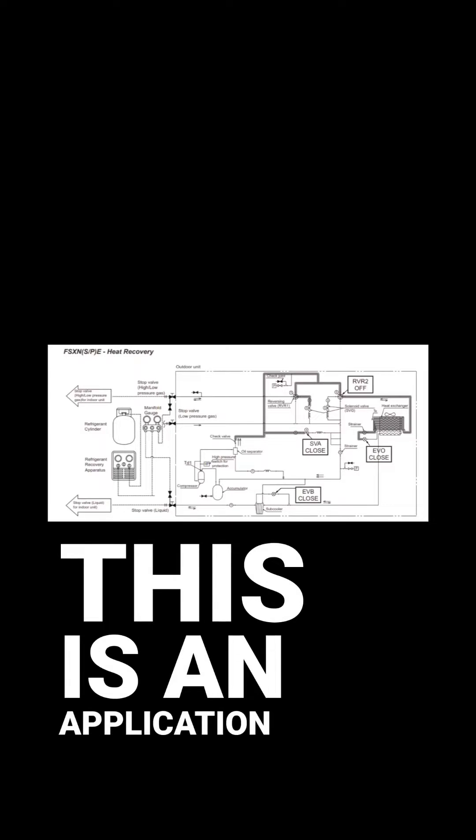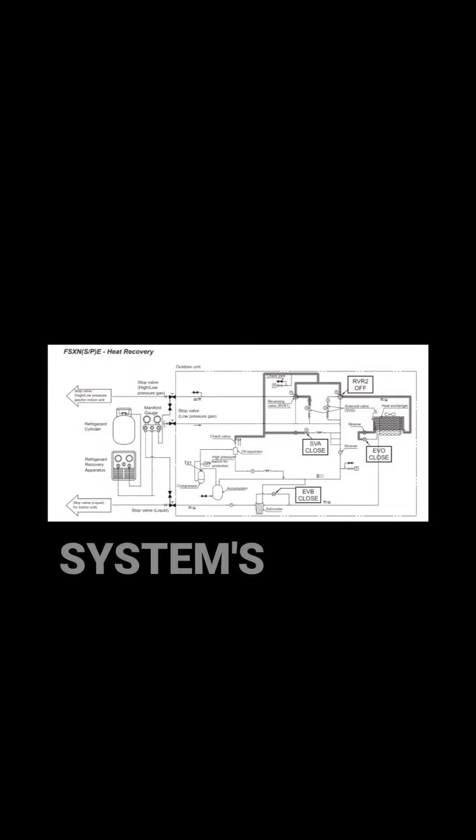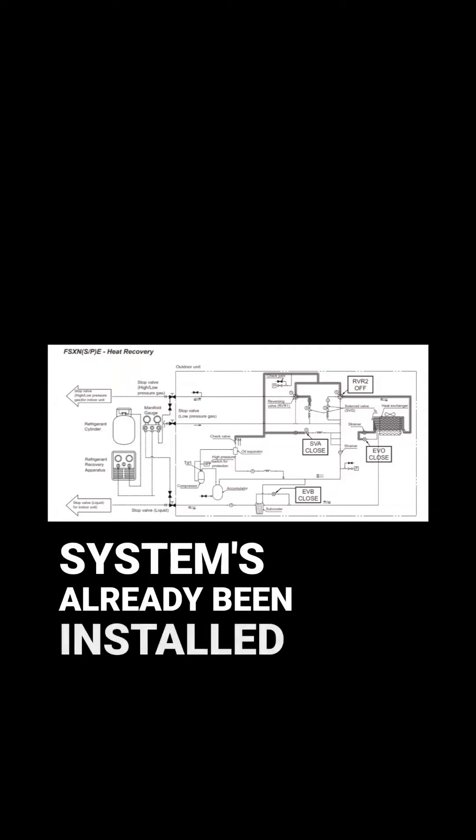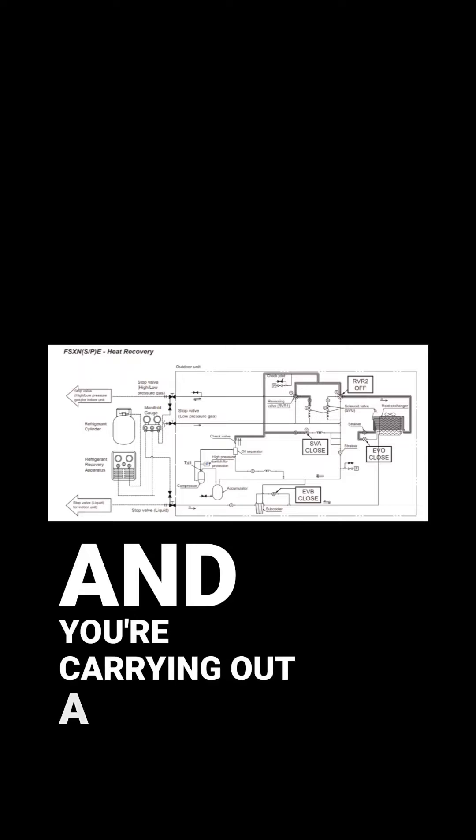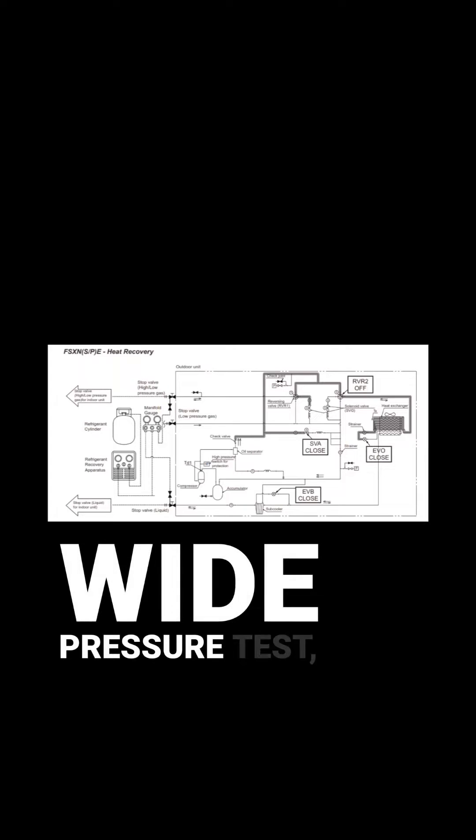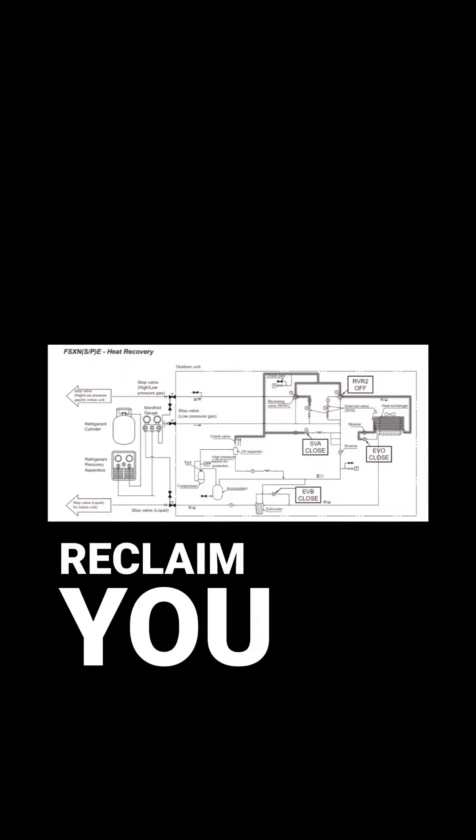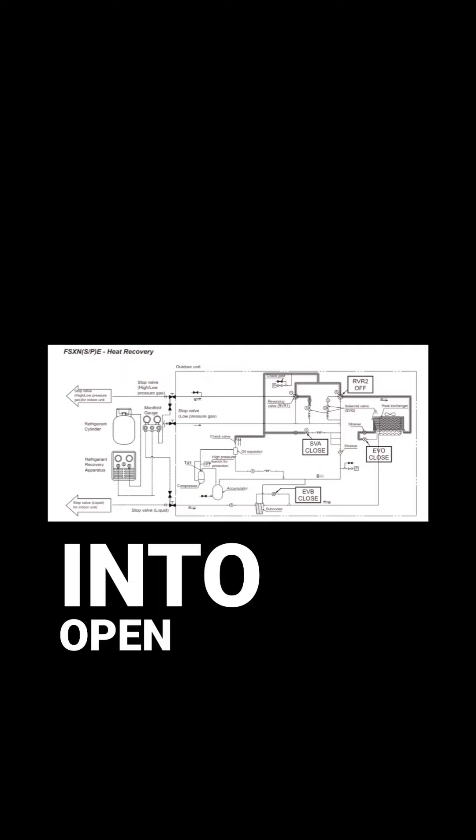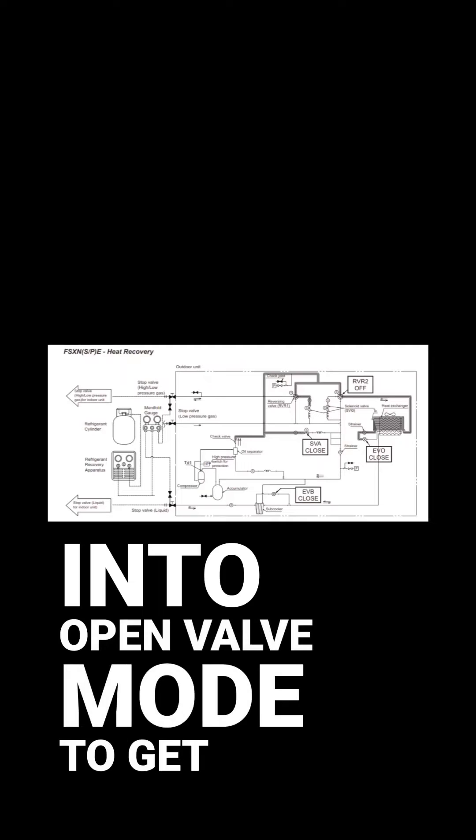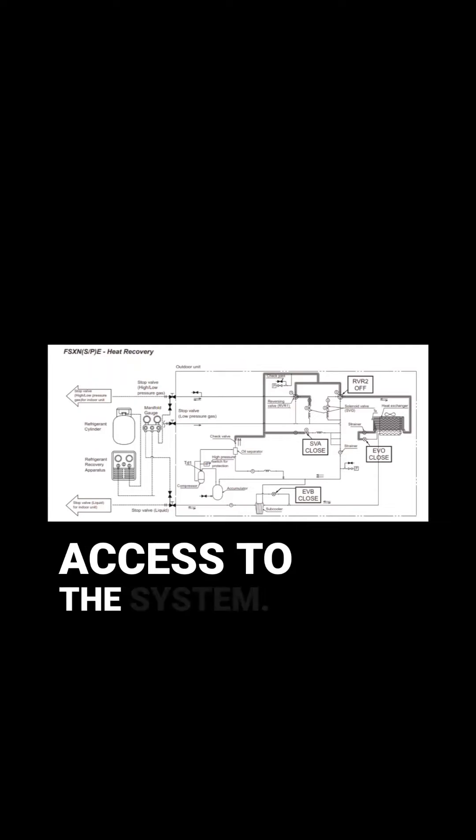If this is an application where the system has already been installed and you're carrying out a system-wide pressure test, evacuation or reclaim, you will want to put it into open valve mode to get full access to the system.